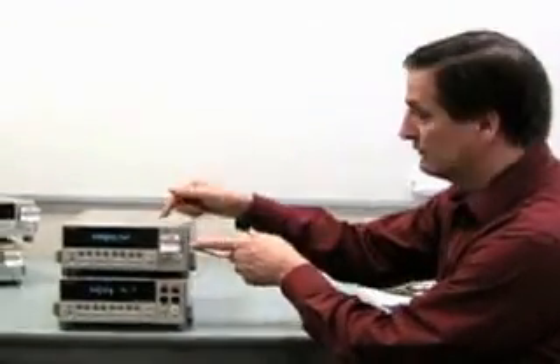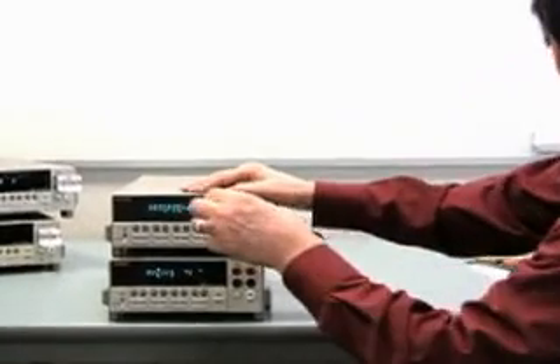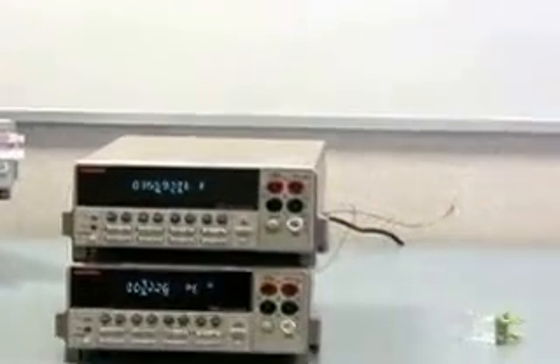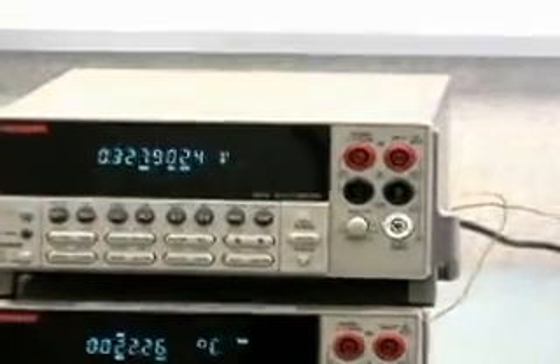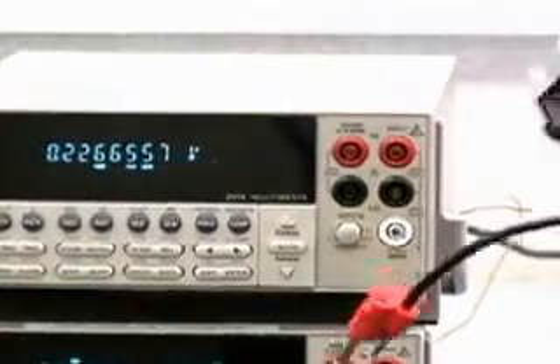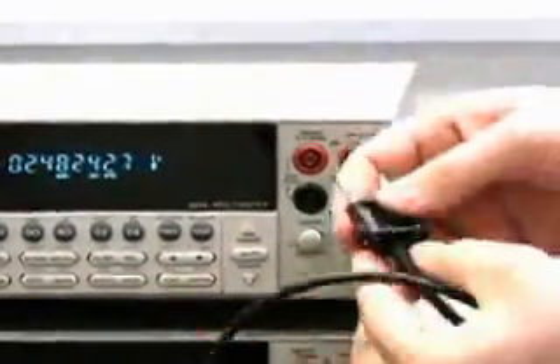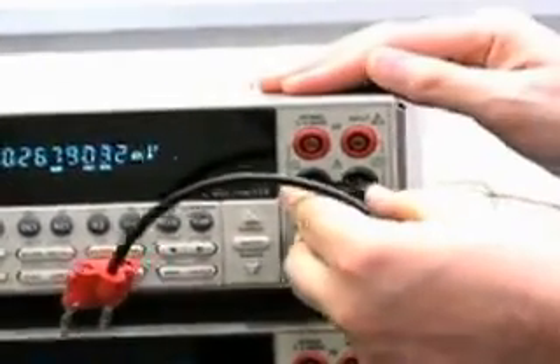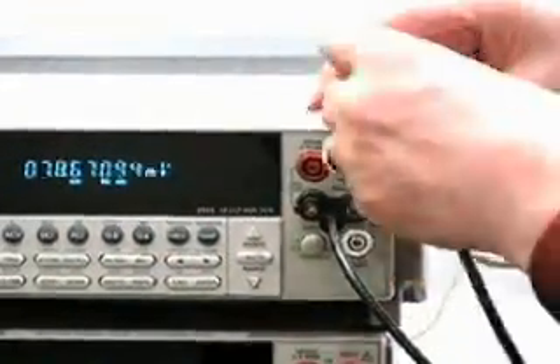Since it is a low noise box, one of the things we can do is measure four wire ohms very, very accurately, because when you're measuring low resistance, you're really measuring low voltage. Let's hook up something to show you that. Now I'm going to show you right here. I'm going to take that off. I'm going to put on a set of test leads known as Kelvin test leads. These are our high-end Kelvin test leads into the instrument.